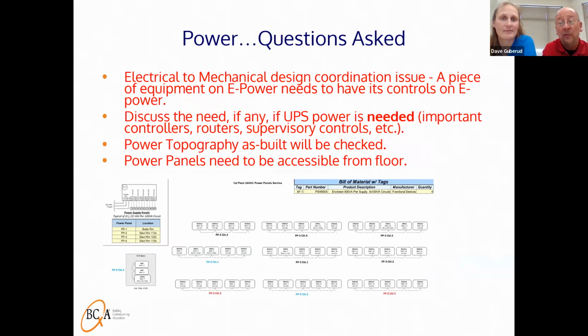So the same thing holds true from a power perspective, right? Making sure that electrical equipment, pumps, hot water pumps, boilers that were on emergency power, that the control panels that are operating them are also on emergency power. Similarly, you have an air handling unit with the controls on e-power, but then what about your life safety dampers? Per code, they all need to close when the system's off, but you want them to all open when the system wants to turn back on. So maybe if those aren't on e-power on UPS, having those dampers, you have to think down the system. We always talk about analogies in the forest and the trees, right? So we've got a couple trees, but they all need to function together as a forest to make that work.